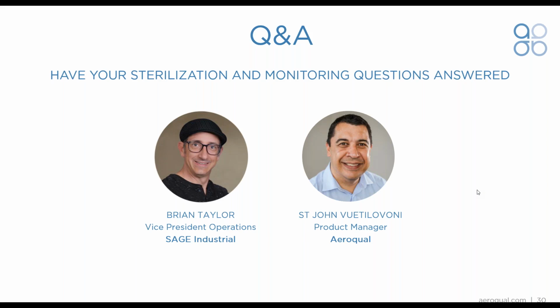Do your monitors read up to 5 ppm? Yes. Our sensors go up to 0 to 10, and we're going to go up to 0 to 30. We also have sensors that go down low, certainly covering up to 5 ppm, and down to 1 ppb as well. So we've got a sensor that can go that low, but it's quite a specific application.